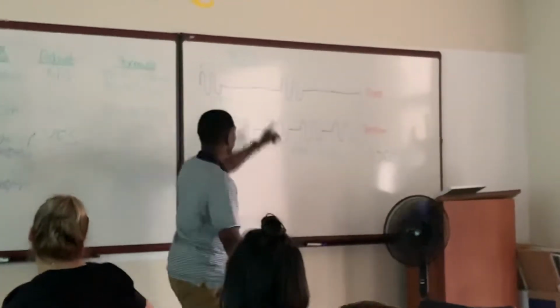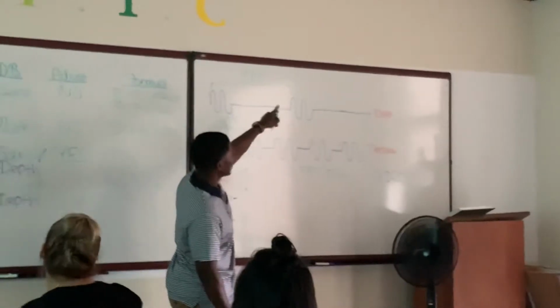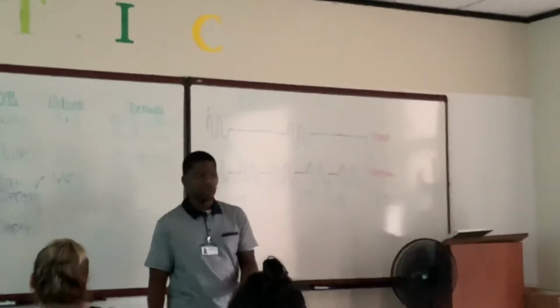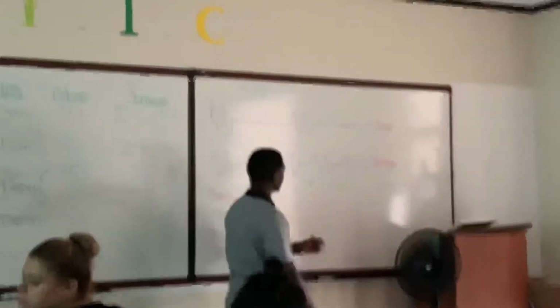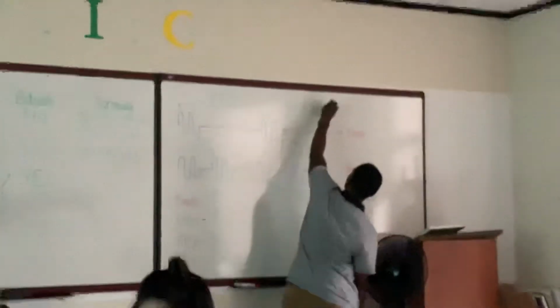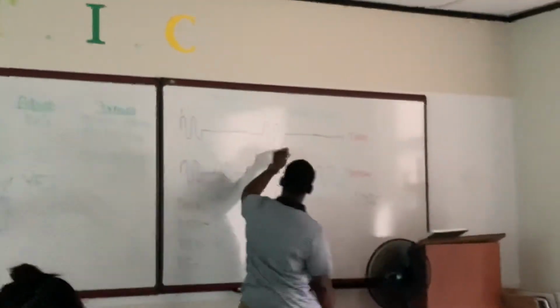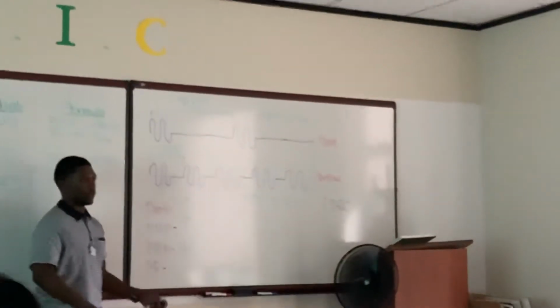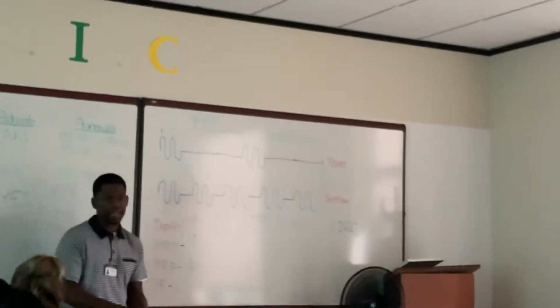Okay. So our PRF on the top one is what? 2 hertz, or 2 pulses per second. So our PRF right here equals 2 hertz, because I have 2 pulses occurring in that 1 second with my deeper imaging, because I have to listen.